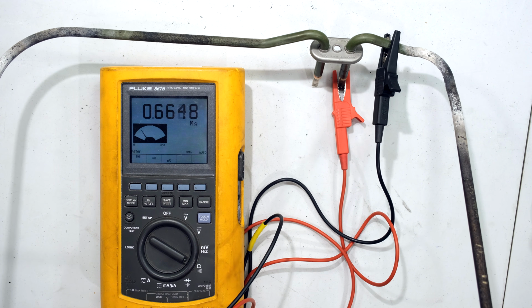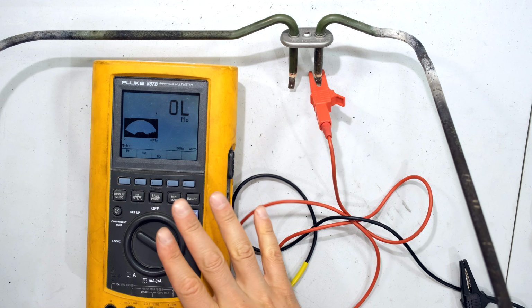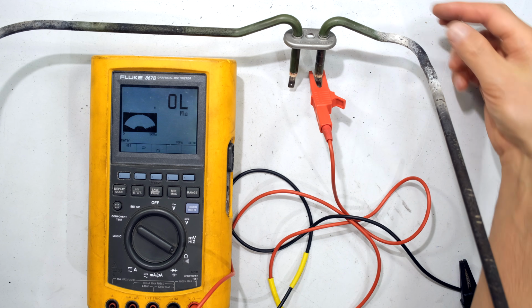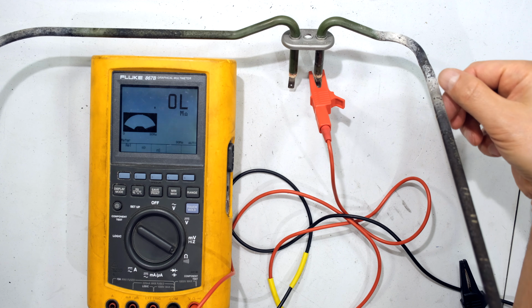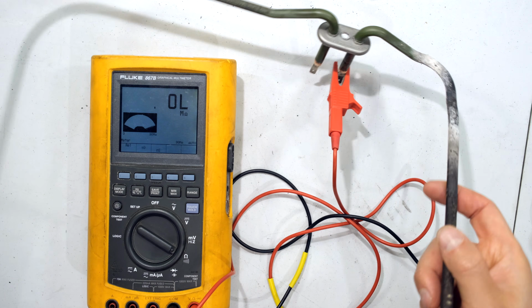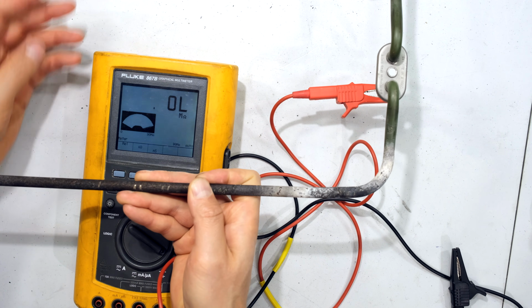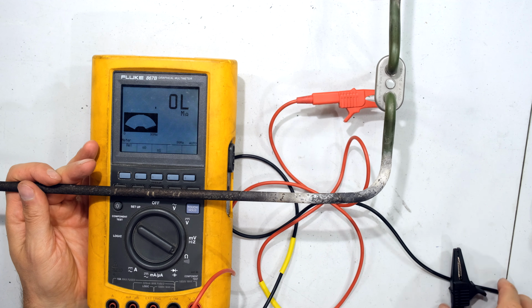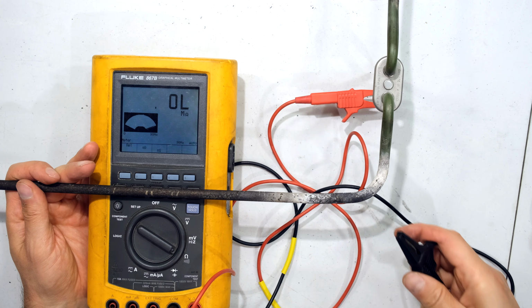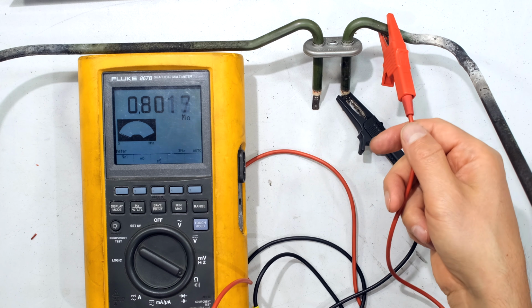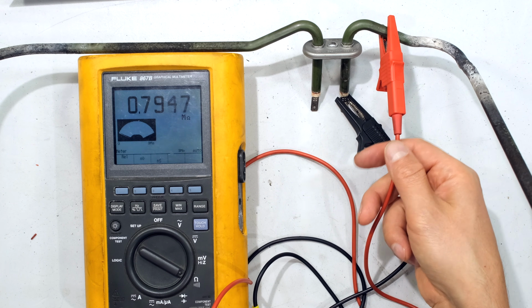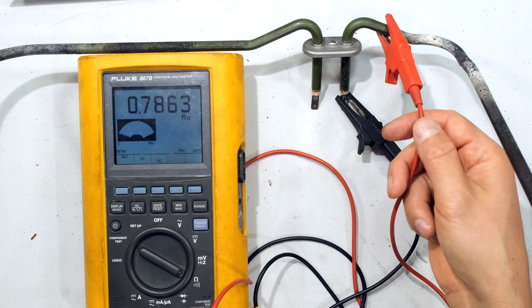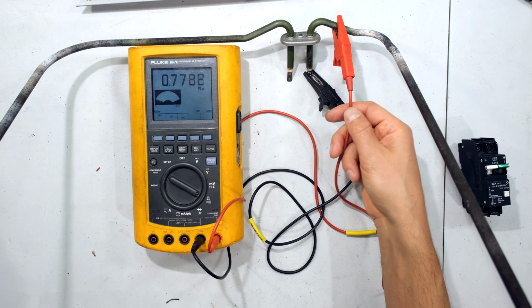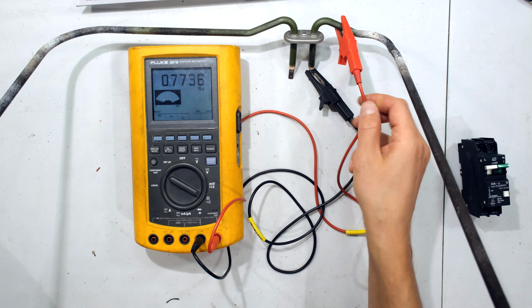Right, so having a look at my meter, I have my crocodile lead there, I'm measuring resistance, and I'm going to just measure the resistance around this element. So I'm going to start here quite close to where the damage is. There is a bit of damage here, and there's the multimeter, and there we can see it's just less than a mega ohm there. It's about 780 kilo ohms. A little bit of an insulation breakdown there.